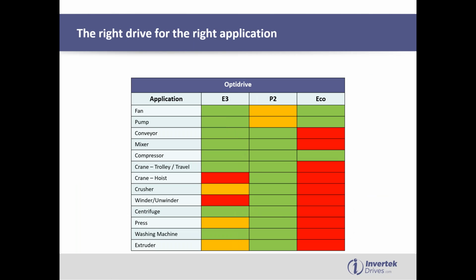So some of the typical applications that we have, I've put together a little matrix. The most common application for any drive is pump and fan. Around 80% of the drives in the world are used on pump and fan applications. So I created this little matrix. It's like a traffic light system. Green means yes, the drive is perfectly suited. Amber or yellow could mean that we have a product that's better suited, and red means the product is not suitable for that application.